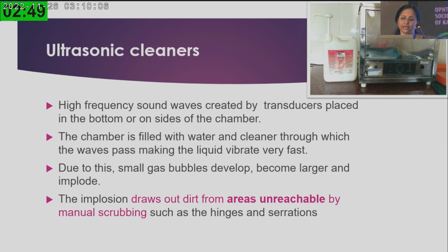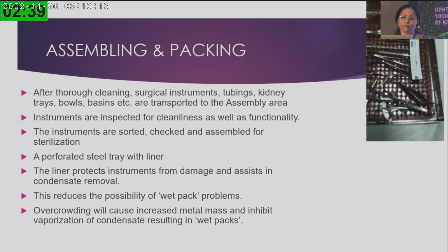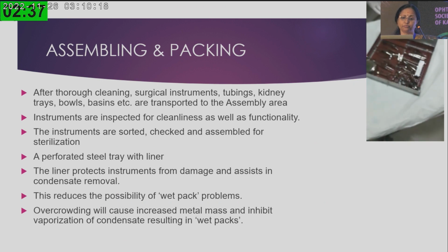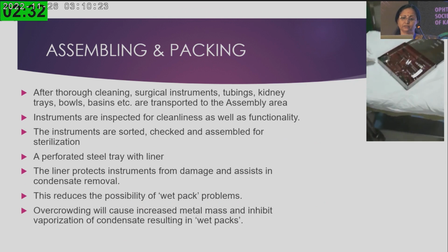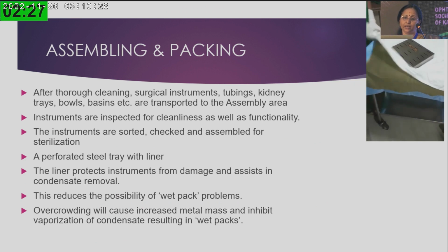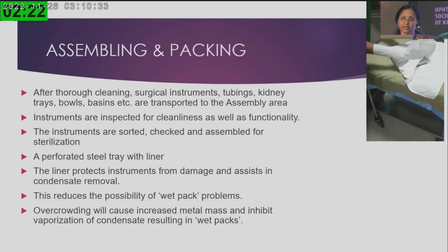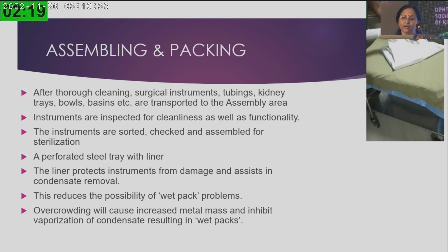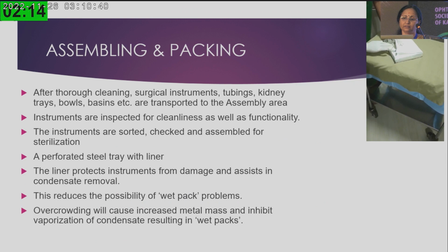And ultrasonic cleaners will help you to remove even the tiniest speck of dirt from unreachable areas like hinges, serrations, etc. And always after thorough cleaning, it should be inspected for cleanliness as well as functionality. And after cleaning, all the instruments are sorted, checked and assembled for sterilization. And always they are put in the perforated steel trays with a liner which will prevent damage of tips, and you should pack them well so that wet packing is prevented.